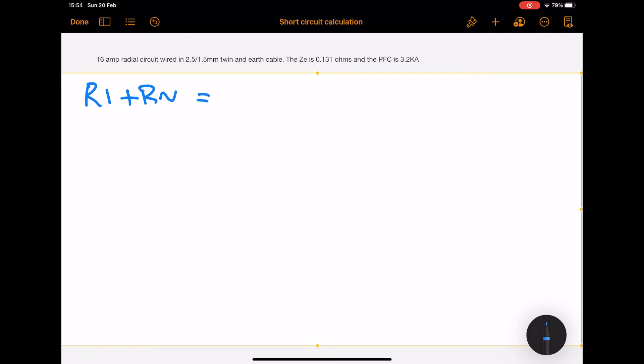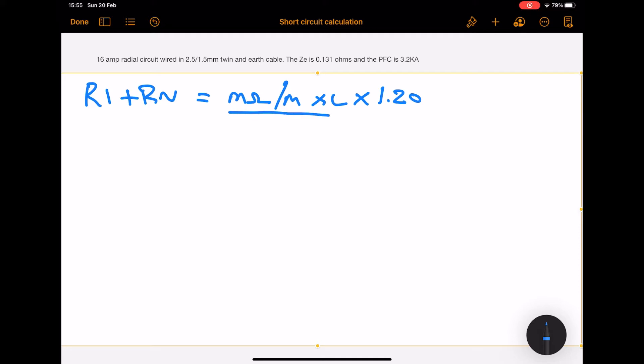Firstly we're going to do the R1 plus Rn. We take the values for milli-ohms per meter from the on-site guide, multiply that by the length, then multiply that by a correction factor of 1.2 to adjust for operating temperature, and then divide by 1000.